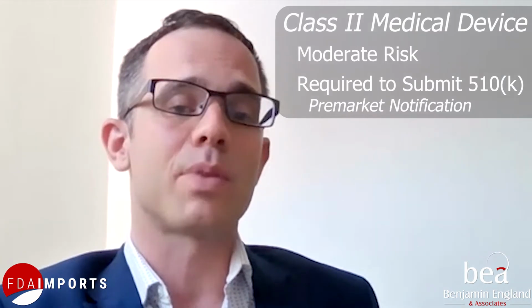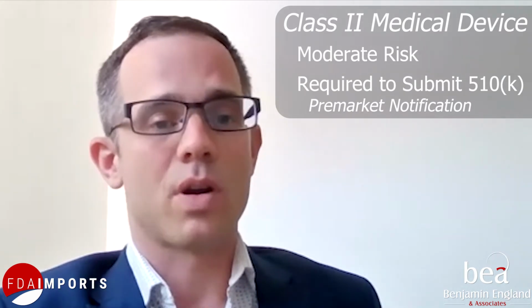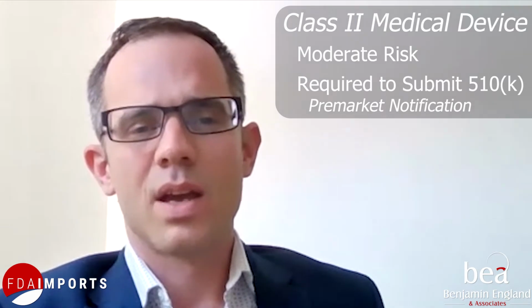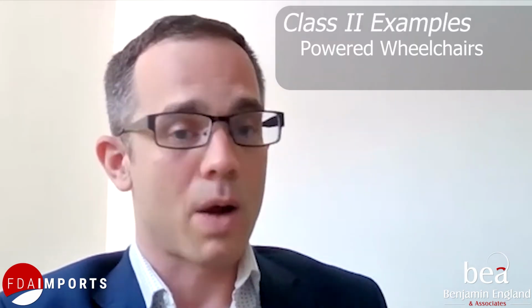Class 2 devices represent a moderate risk to consumers. Generally speaking, manufacturers of Class 2 devices are required to submit a 510(k) pre-market notification before they can market their device in the United States. 510(k) submissions are unique in that they prove that a given device is substantially similar to another device that is legally being marketed in the United States. Examples of Class 2 devices include powered wheelchairs and some pregnancy tests. Manufacturers of Class 2 devices are required to comply with both general controls and special controls.